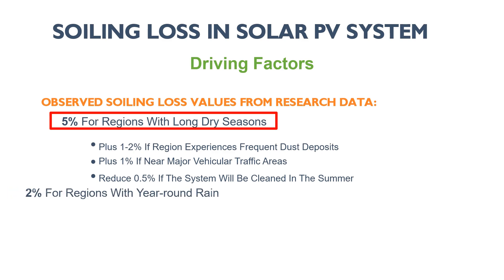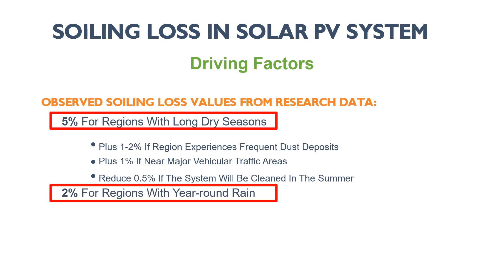Soiling loss values observed from a large number of solar plants throughout the world in recent years are as follows: five percent for regions with long dry seasons; add one to two percent if the region experiences frequent dust deposits; add one percent if near major vehicular traffic areas; remove 0.5 percent if the system will be cleaned in the summer; and two percent for regions with year-round rain.